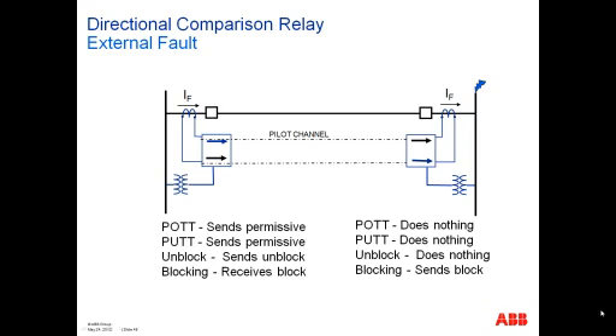For example, a permissive overreach transfer trip, POTT, sends a permissive for an external fault, and at the faulted end where the reverse fault is seen, the POTT does nothing, so there is no trip. A permissive underreach transfer trip scheme sends a permission, but again, since the fault is reversed, the PUTT does nothing. The unblock system sends an unblock signal to allow the local end to operate, but the unblock, seeing a reverse fault, does nothing likewise.